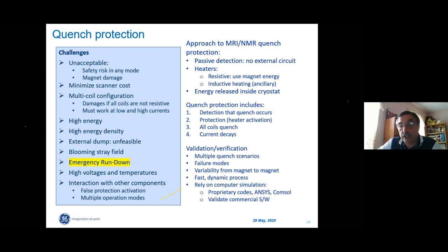What we cannot afford? An external dump. Because an external dump requires a high voltage across current leads. It's not how MRI magnets are designed. It's not compatible with emergency rundown. So we have to dispose of all energy inside the cryostat. So how do we do it? Passive detection, no operator involved. And in a typical MRI magnet, we need to ramp the magnet down at nominal current within, let's say, 1 to 3 seconds.